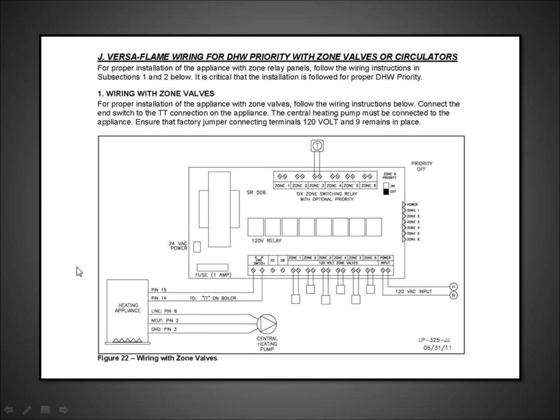This gives you an idea of how the unit would be set. This is a wiring diagram showing the VersaFlame set up with central zoning panel for zoning with DHW priority. And when the paddle switch makes, what's going to happen is this pump gets deactivated and the priority goes to the central heating, the DHW pump, which is connected to the brace plate inside of the VersaFlame.